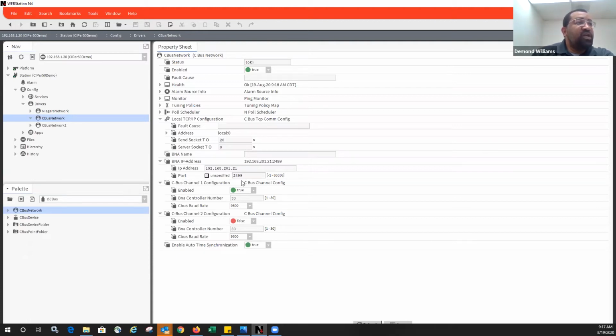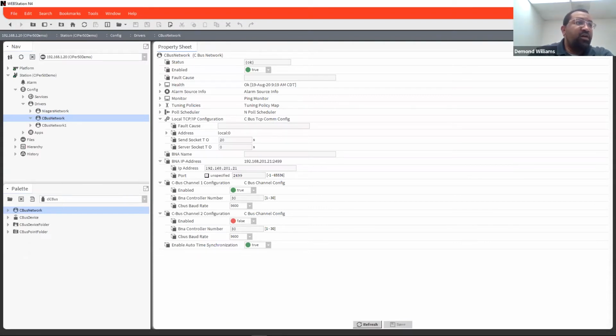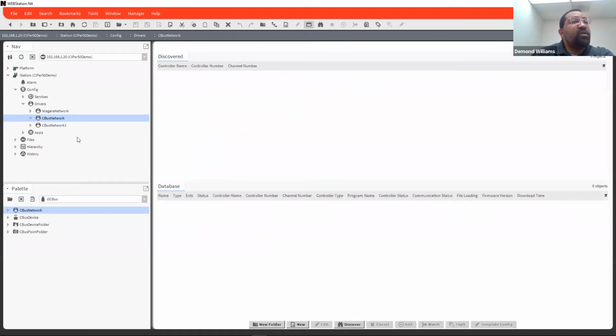The C-bus channel 1 configuration basically is where you set the baud rate. Most Honeywell controllers, the XL10 lines, everything was left at a default C-bus polling rate of 9600. If you find any that were running faster than that, they tend to cause you issues on that network. So all the networks were pretty much left at 9600 baud. Once you have this set up and your network status is okay, just like any other network, you can double click on the C-bus network, and then you want to go here and just do a discover.